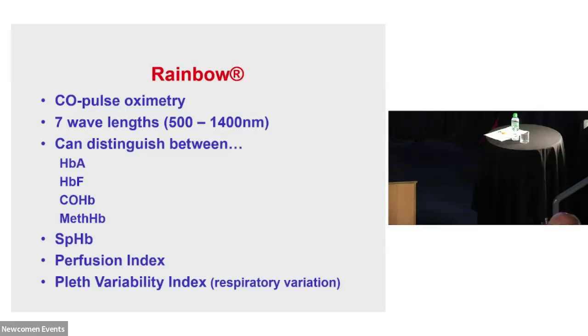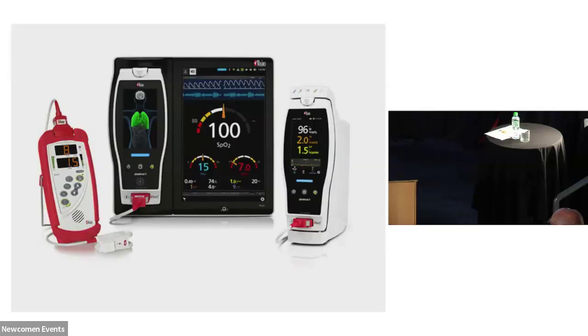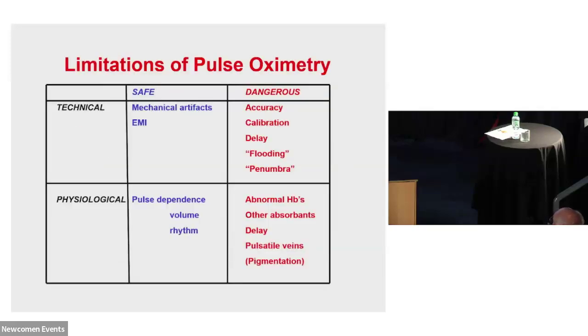And because of that, these much more expensive rainbow pulse oximeters can distinguish between the other, and will actually indicate how much HbF there is. That's fetal hemoglobin, carboxyhemoglobin, methemoglobin. And in fact, it will guess what the hemoglobin concentration is. So ideally, all pulse oximeters should have 7 wavelengths or more in them. And that covers that problem there.